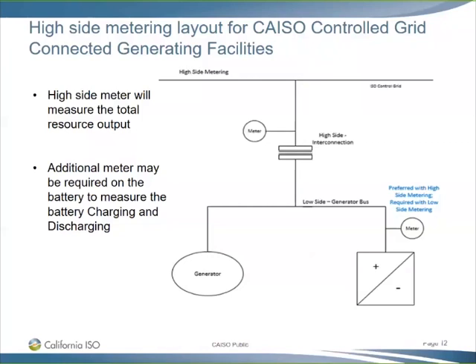So on slide 12, the additional meter on the storage unit is for RPS reporting purposes. Most resources prefer ISO to be their QRE coordinator and want ISO to report to WREGIS, so that additional meter needs to be an ISO meter. If the resource wants ISO to be their QRE coordinator, it becomes an ISO requirement to have the additional meter. But if the entity prefers ISO not be their QRE coordinator, then it's not an ISO requirement to install the meter. They can use another methodology to calculate and report to WREGIS without an ISO meter.